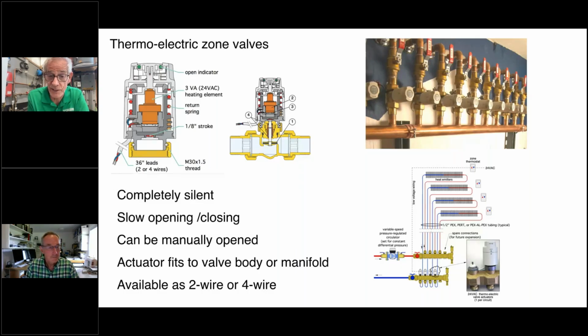Now, in the past, you could only get 3 of them, maybe 4 of them on a 40 VA transformer. So it took a lot of power if you had a bunch of them, like you see on the wall there. But now we've got them down to a much lower current draw. The trade-off, of course, is it takes a little bit longer to open because you've got less current going to heat up that wax in there. So a little bit slower, but you can get more of them on your relay box or on your transformer if you're wiring them up that way.